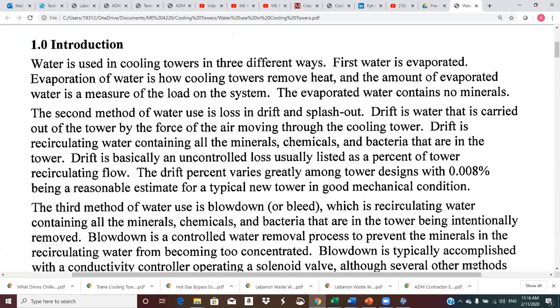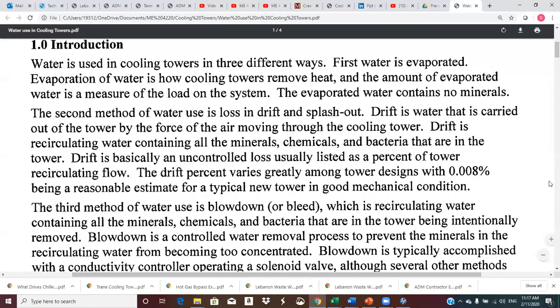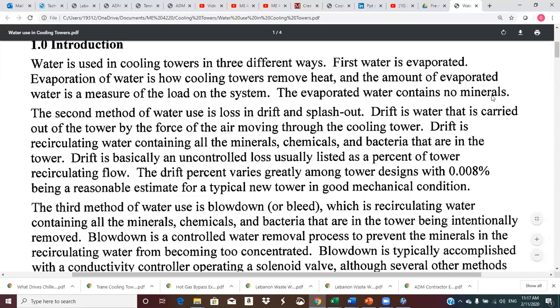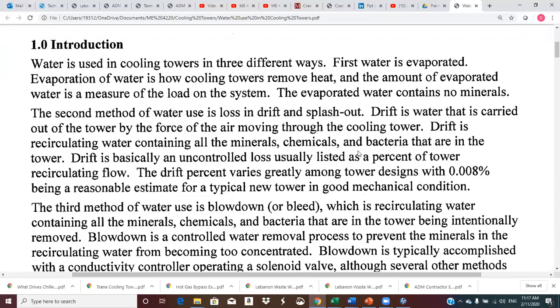Okay, so we start off with three different uses of water in cooling towers, and the first would be evaporation, and that's the whole point of the tower, to promote evaporation, to cool the water stream, the heated water stream coming in, so we can drop 10, 15 degrees out of it and return it to a chiller or some sort of an industrial process. We should note that this evaporated water contains no minerals, so it should be pretty pure when it evaporates. It leaves all that stuff behind.